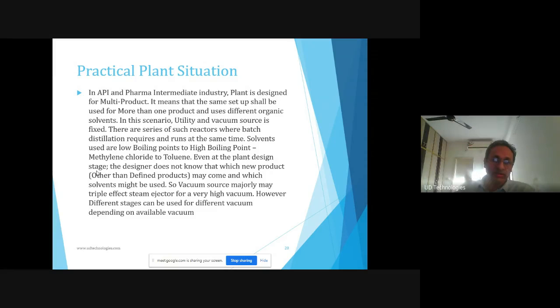There is a series of such reactors where batch distillation requires and runs at the same time. In a single plant there may be a number of batch reactors, with the same process or different processes and products, but when we design, we cannot have a different vacuum source or different utility for each reaction. So generally they use the cooling tower in the primary condenser, in the secondary condenser they may use chilled water, and if more is required, then they go for brine at minus temperatures.